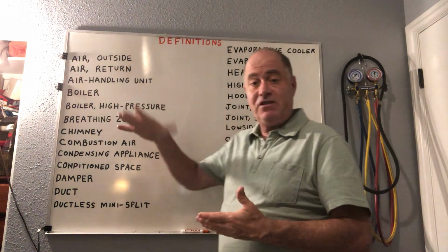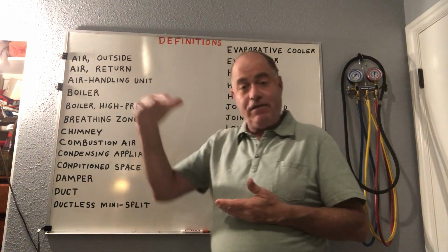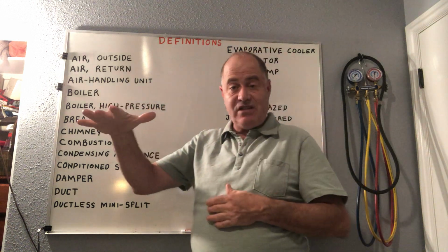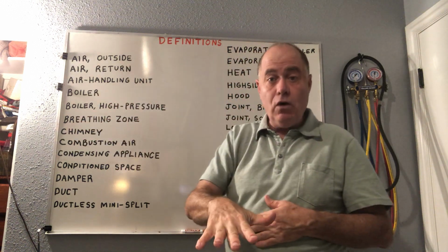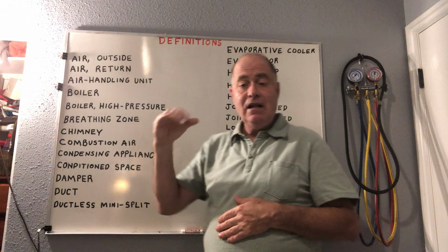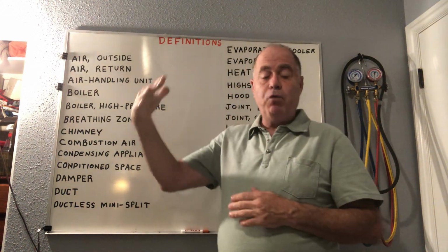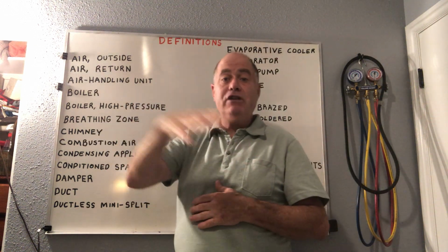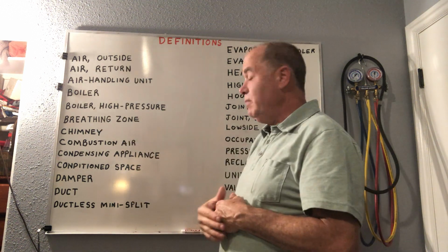which is just the opposite of everything I just said. 15 psi of steam pressure and below, it's a low pressure boiler, right? If you're just heating up water to 250 degrees or below, low pressure boiler.